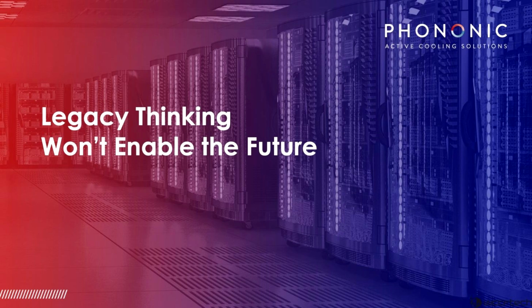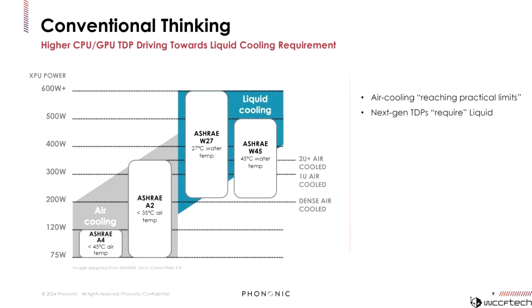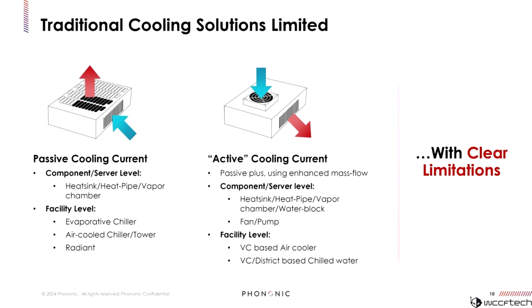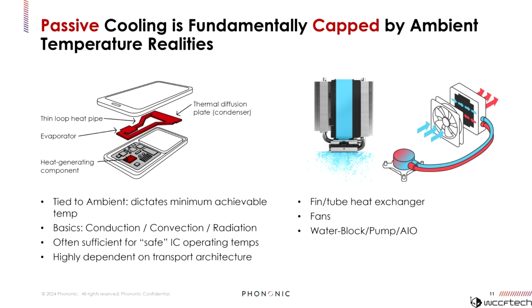The cooling requirement in the tech industry is growing rapidly. Modern AI data centers require more cooling capability, leading to bigger, power-hungry solutions to sustain them. Previous generation data centers consumed 40 kilowatts per rack, and the upcoming generation will consume around 120 kilowatts per rack, a 3x increase. Even with the best-case solution, the industry can only achieve 66 kilowatts per rack due to cooling limitations. 40% of the power budget in data centers goes toward thermal management, so it's time companies invest in innovative solutions to sustain themselves.